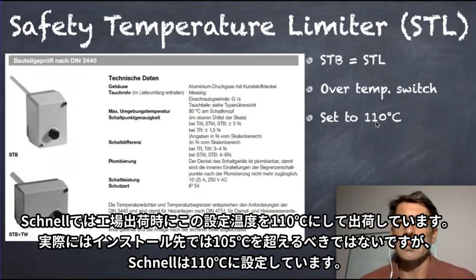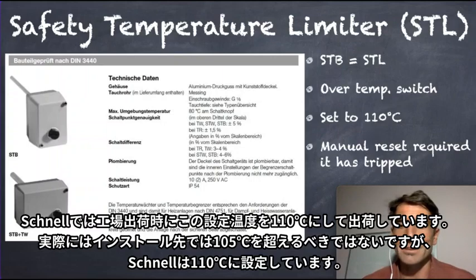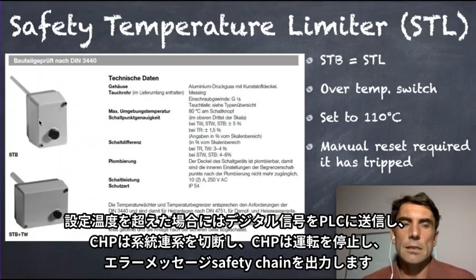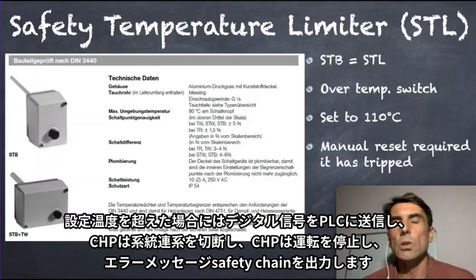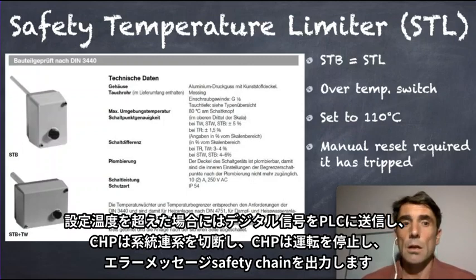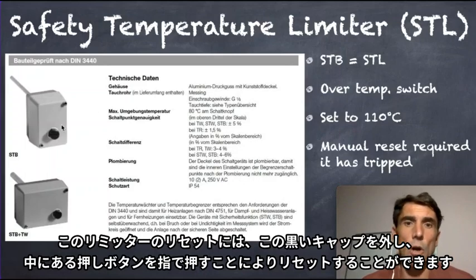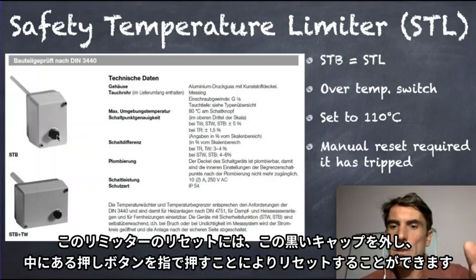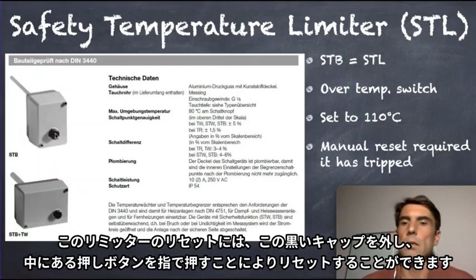This is the target or the setting of Schnell. I think most of the system should not exceed 105 degrees Celsius, but yeah, it's the setting of Schnell. If we exceed the temperature, the switch will open the contact and send a digital signal to the PLC, and the CHP will stop with an error message or safety chain error. To reset this temperature switch, we have to remove the black or gray cap here, and underneath there is a switch that you can press with your finger to reset it.